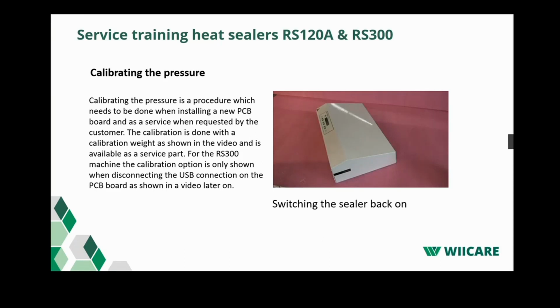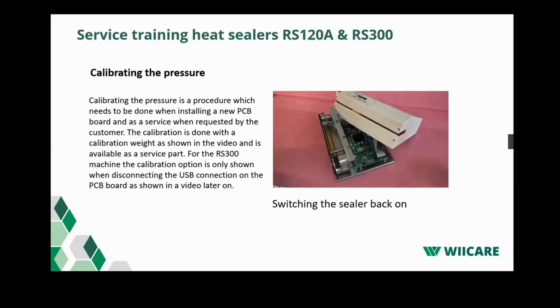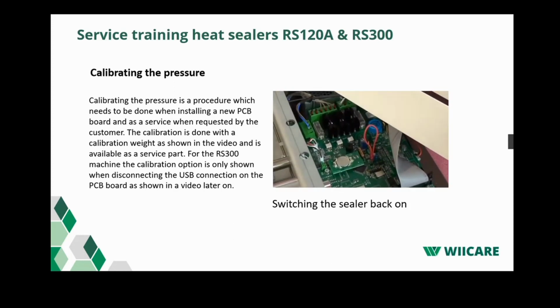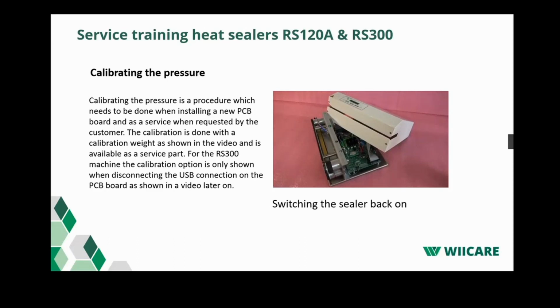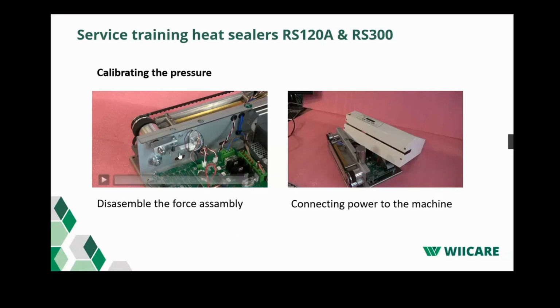In this video, I will show you how to calibrate the force. First, remove the hood. I already removed the screws at the bottom. To be able to calibrate, a jumper must be placed on the PCB. Okay, so we go to the next video. Disassemble the transmission force assembly.